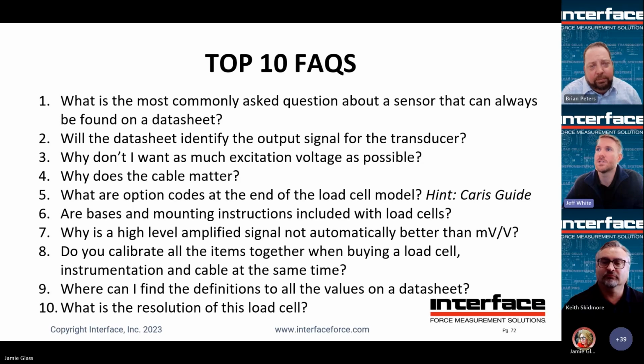Why don't I want as much excitation voltage as possible? Well, every load cell has a spec for how much excitation it will handle. You start putting more excitation in there, you're heating up the load cell. More is not always necessarily better. 5 or 10 volts is normally fine. And then it does get into, how much signal am I going to get back? Modern data acquisitions can normally decipher a very low signal, and they've gotten very good. So you don't always want to just maximize the excitation.